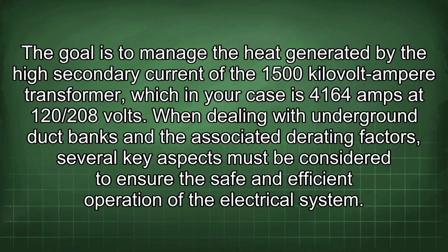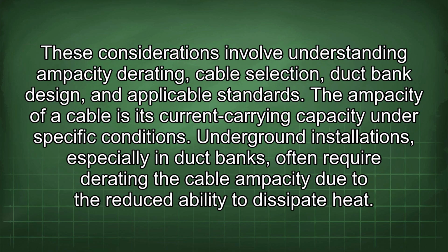The goal is to manage the heat generated by the high secondary current of the 1500 kVA transformer, which in your case is 4164 amps at 120/208 volts. When dealing with underground duct banks and the associated derating factors, several key aspects must be considered to ensure the safe and efficient operation of the electrical system. These considerations involve understanding ampacity derating, cable selection, duct bank design, and applicable standards.